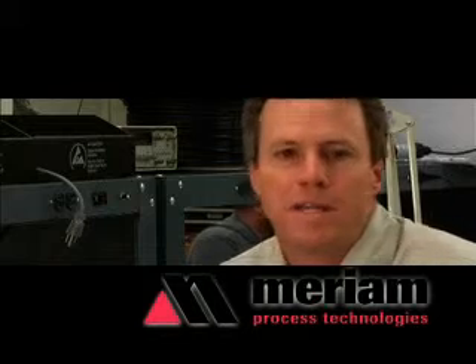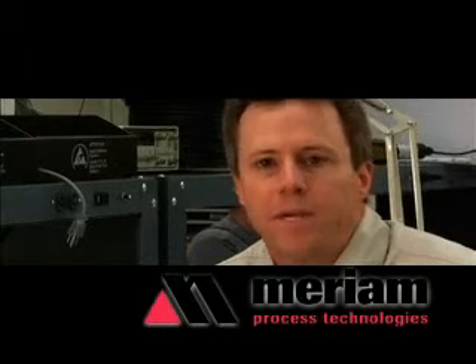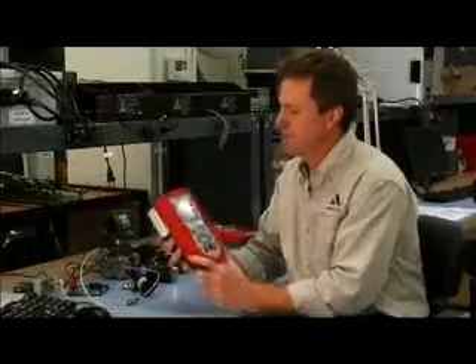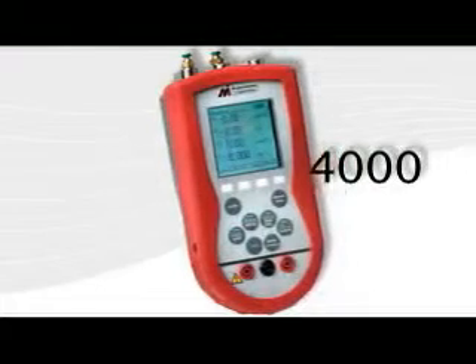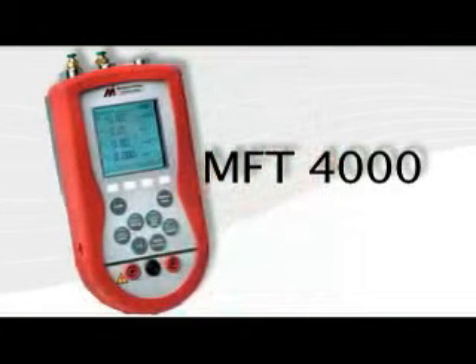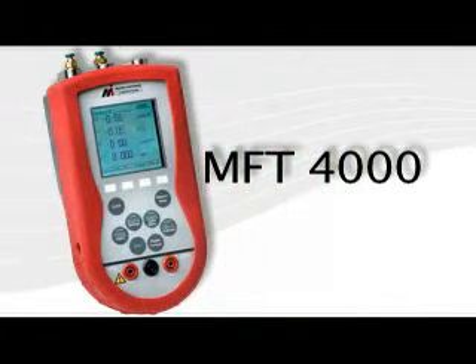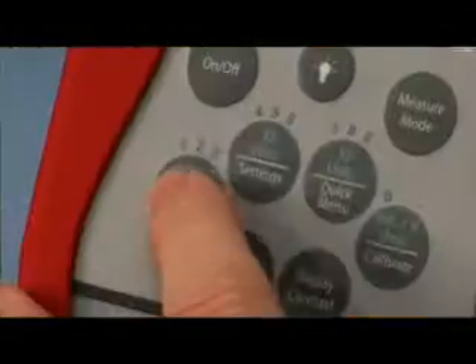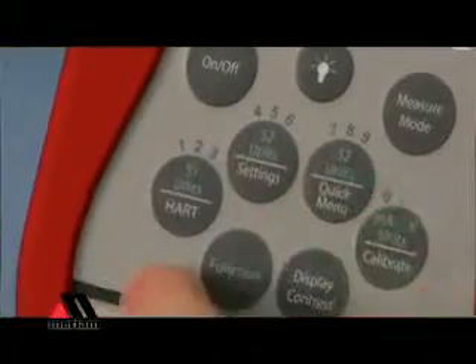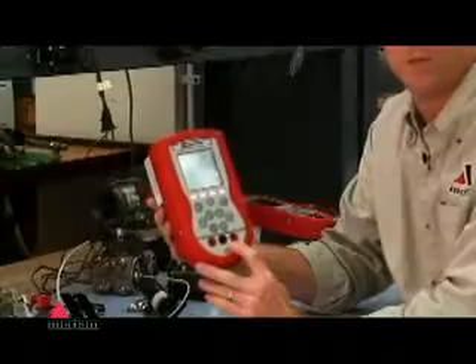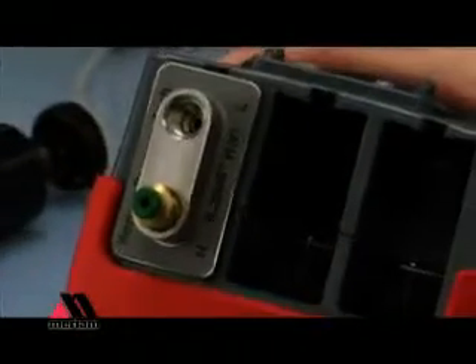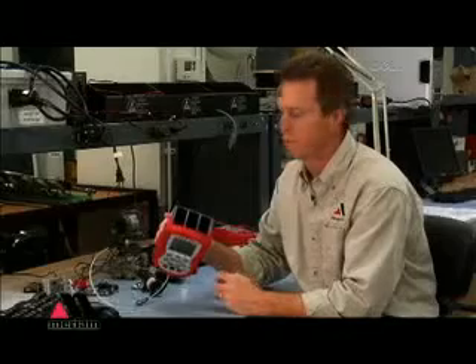The MFT was designed to be the one tool that I&E technicians need to handle any application they may come up against during the course of their day. The base unit is the MFT 4000. The 4000 stands for calibration only, and it consists of a display, a keypad for the user interface, voltage and current measurement, bays for up to 3 different modules, and a protector for bays that you don't use.